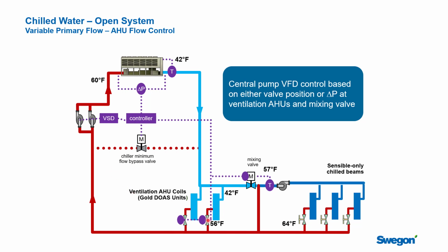And again, you could do the same thing. You could look at the position of these valves and make sure that none of these valves get more than 90% open. If they start to get close to that, then you increase the flow. If they start to get a lot more closed and they're throttling down, then you can drop back the pressure and slow the pumps down.